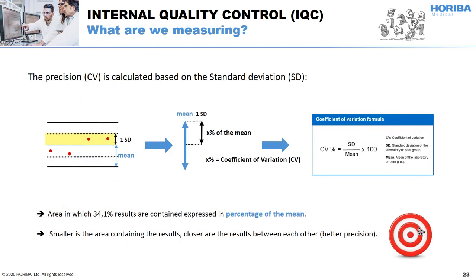What are we measuring? The precision calculation is based on the SD. 1 SD is the distance from the mean, and this gap includes 34% of the results. If the value of 1 SD is smaller, the 34% of results within this gap will be mechanically closer to each other and the precision will be better. The SD expressed as a proportion of the mean gives the coefficient of variation, which reflects the precision. The smaller the CV, the better the precision.